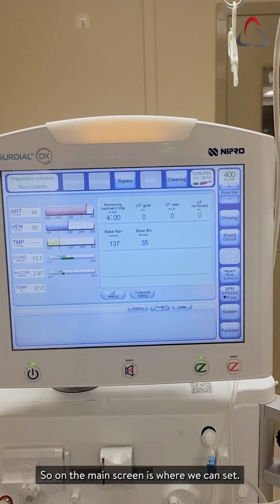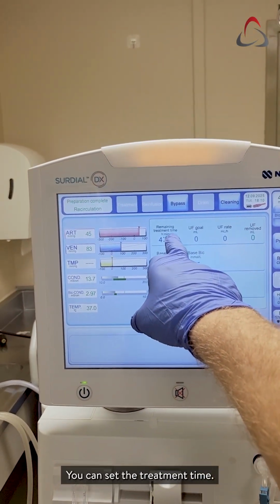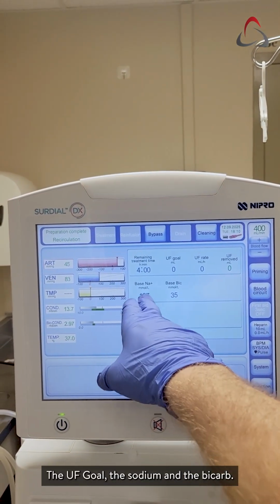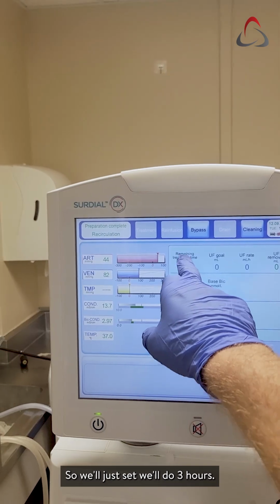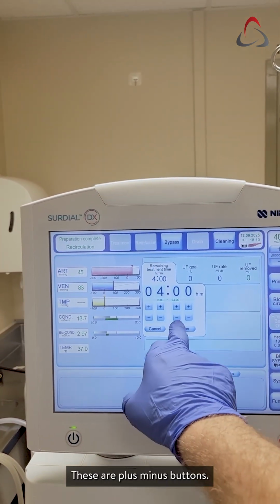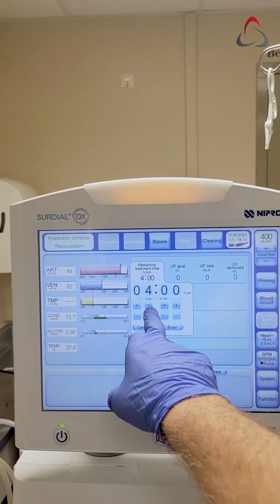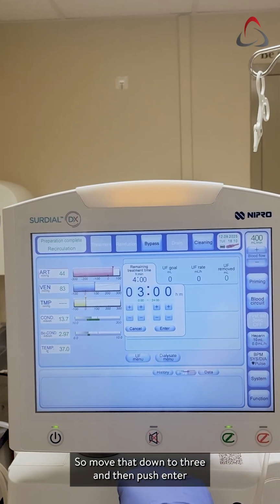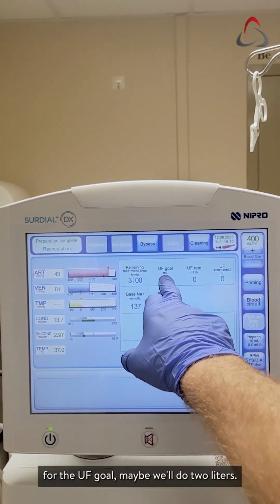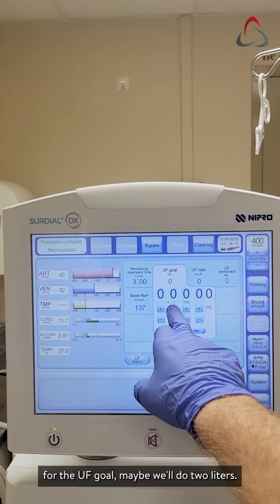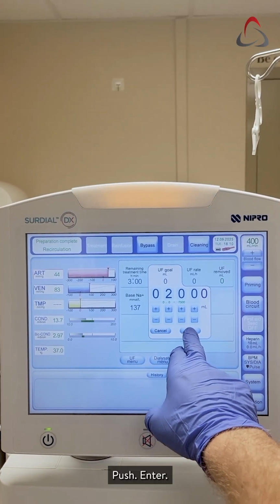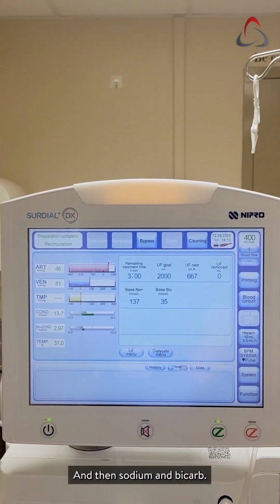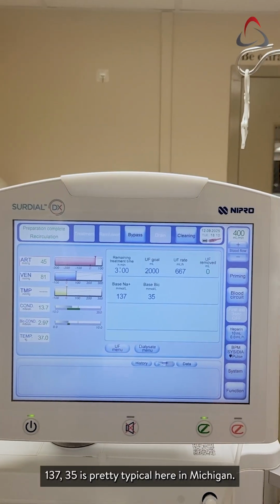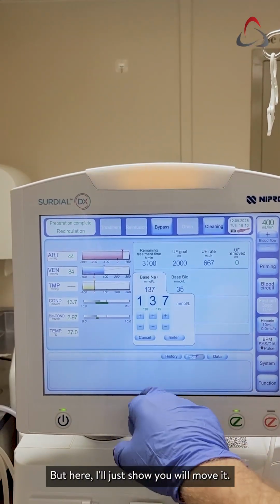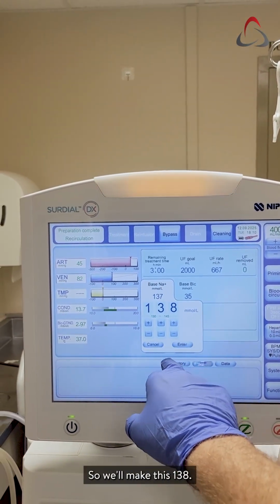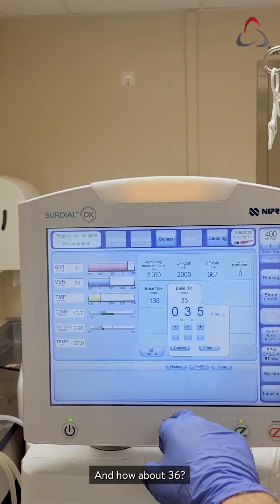So on the main screen is where you can set the treatment time, the UF goal, the sodium, and the bicarb. So we'll do 3 hours. These are plus minus buttons. So move it down to 3 and then push enter. For the UF goal, maybe we'll do 2 liters. Push enter, and then sodium and bicarb. 137, 35 is pretty typical here in Michigan, but here I'll just show you. We'll move it, so we'll make this 138, and how about 36?